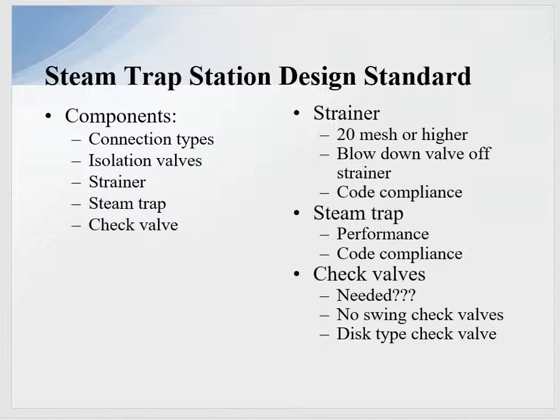What do I mean by code compliance? If the operating system is 150 psi at 366 degrees and I put a steam trap rated right at 150 psi and 366 degrees — am I in code compliance? Probably not. Because the safety valve protecting the system is set at 250 psi. You have to have all steam trap station components — isolation valve, steam trap — meet that safety valve setting. It's not operating pressure that determines code compliance; it's the safety valve setting.